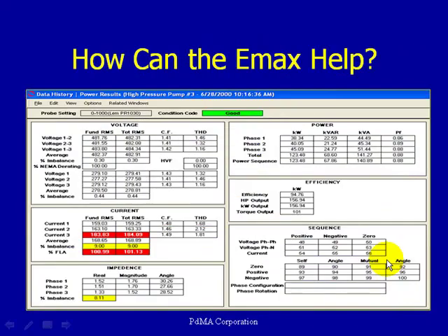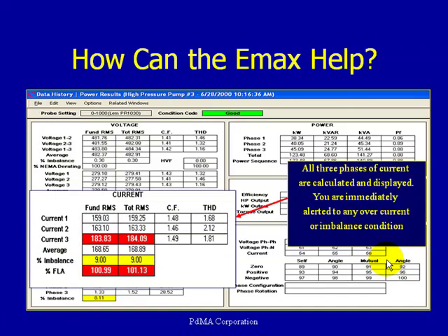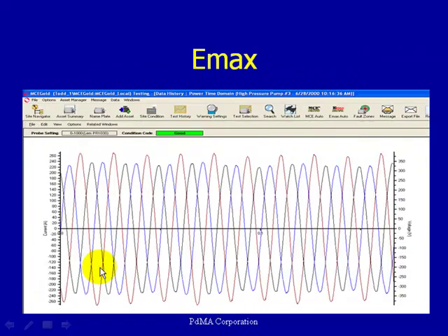What if the motor is running? We calculate all three phases of current, and you're immediately alerted to any current imbalance — highlighted in yellow or red. In this case, we're above our percent full load amps, so the software color-codes that condition for you. A current imbalance is not healthy for the motor and potentially causes overstress. We can also view this in the time domain, monitoring current on all three phases to visually confirm the imbalance.